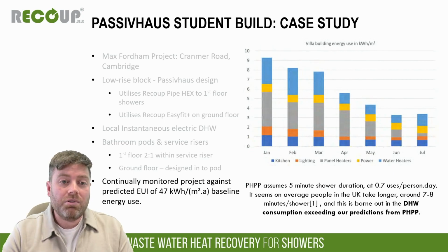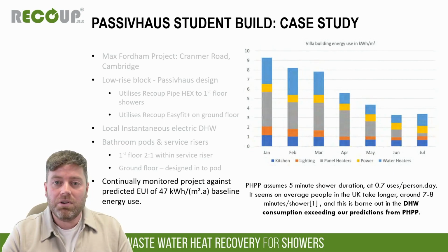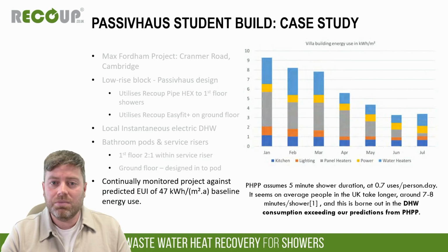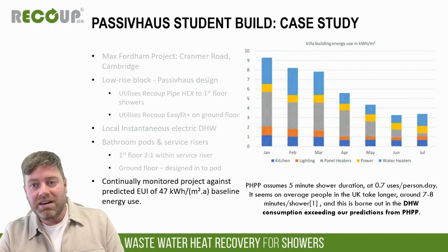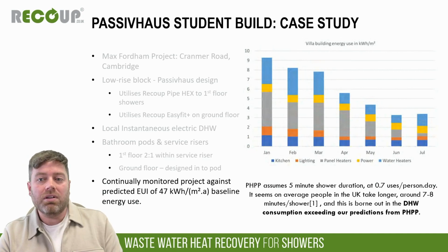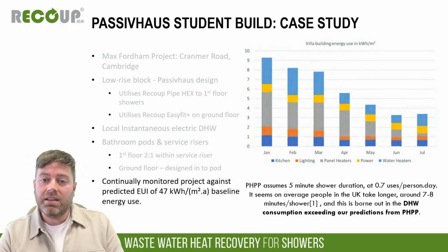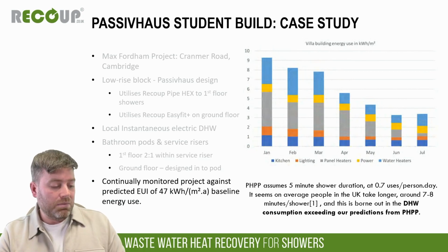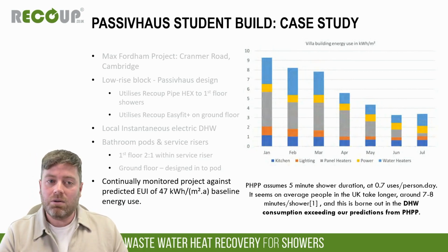It was a continually monitored project, tracking the energy use. The initial data showed actual hot water use was more than expected, but that's because the PHPP software used for modelling assumes a 5-minute shower duration, while students actually shower for around 7 to 8 minutes on average. So hot water use is higher than expected, but that means the wastewater heat recovery is having even more impact.